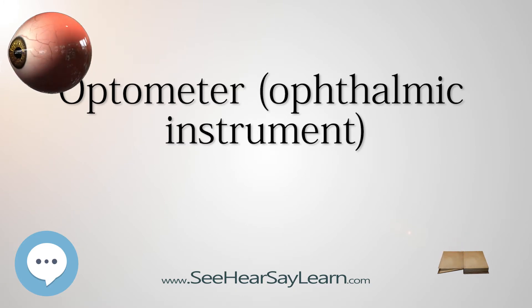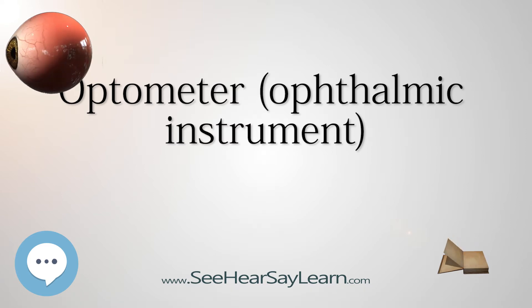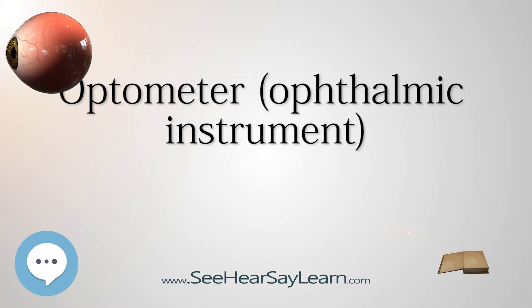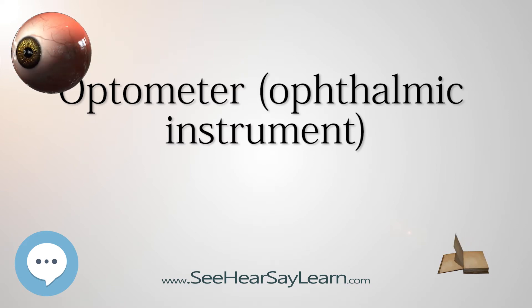A phoropter is one of several generic names for modern instruments containing an optometer, a battery of lenses for determination of optical error, combined with prisms and other attachments for measuring binocularity. The term refractor is another such term, and vision tester or other descriptive terms are used because phoropter, spelled with 'or', is actually a trademark of one company.